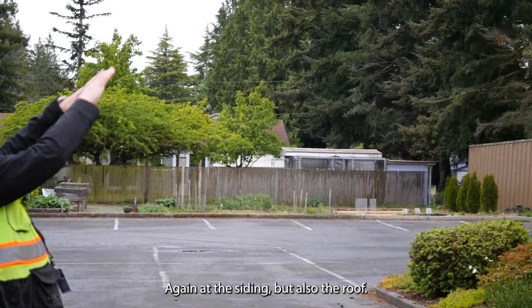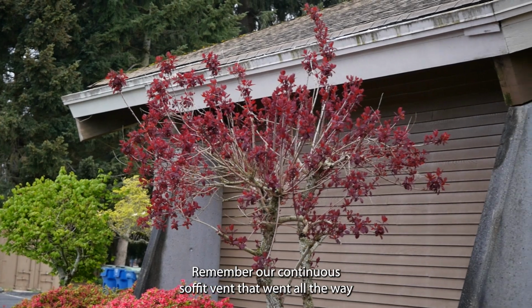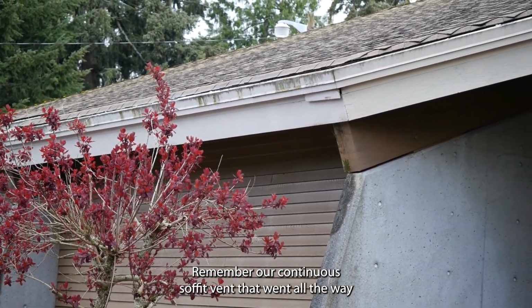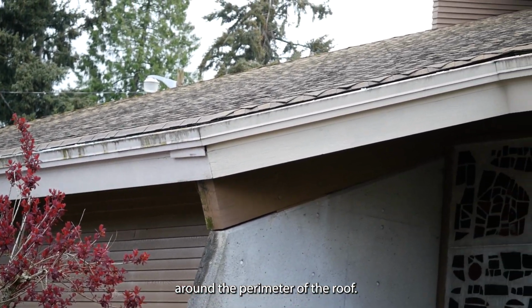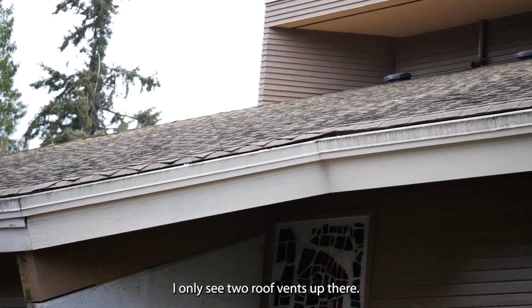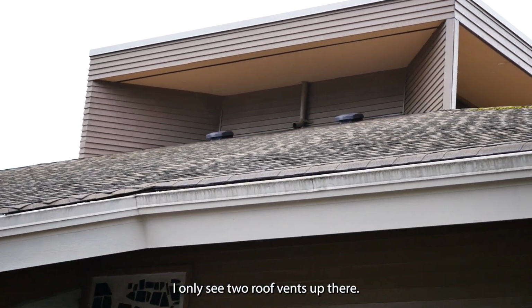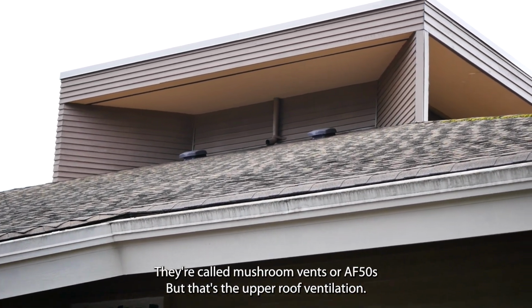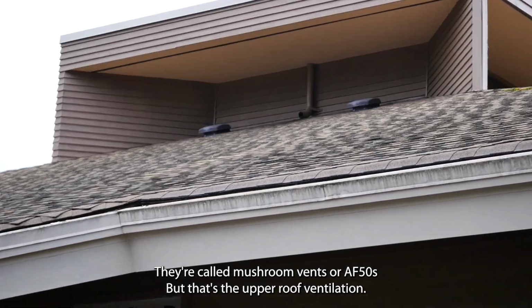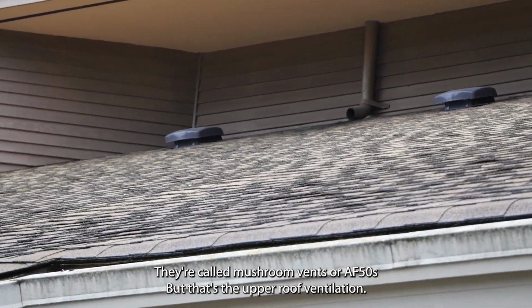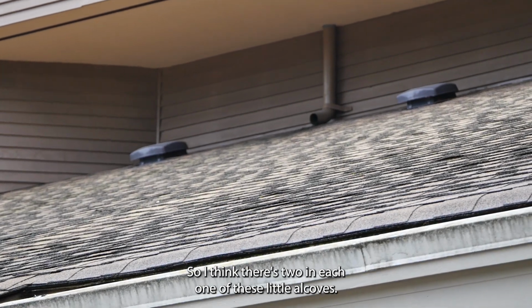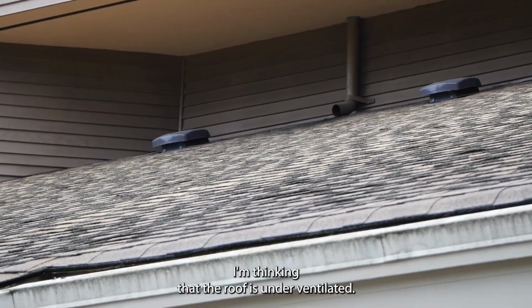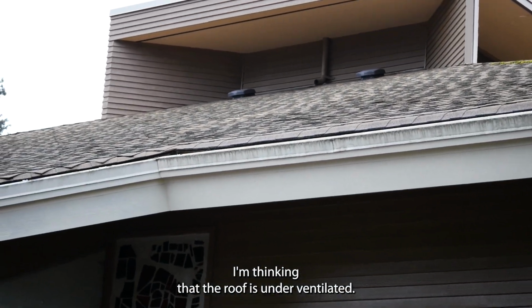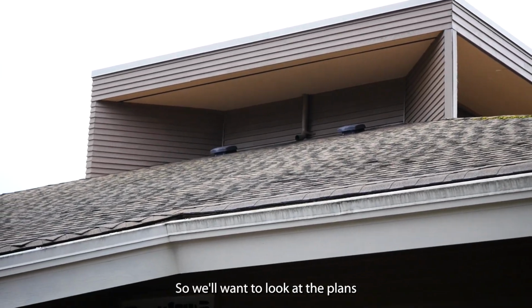Again, at the siding, but also the roof. Remember our continuous soffit vent that went all the way around the perimeter of the roof. I only see 2 roof vents up there. They're called mushroom vents or AF50s, but that's the upper roof ventilation. So I think there's 2 in each one of these little alcoves. I'm thinking that the roof is under-ventilated. So we'll want to look at the plans.